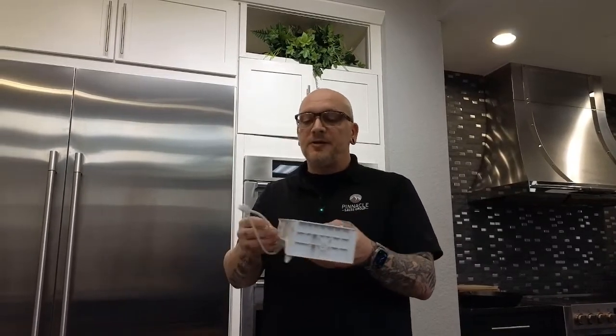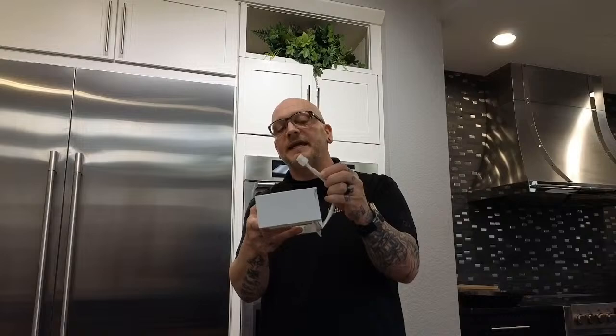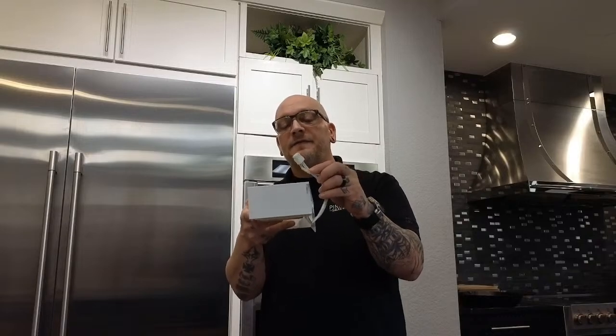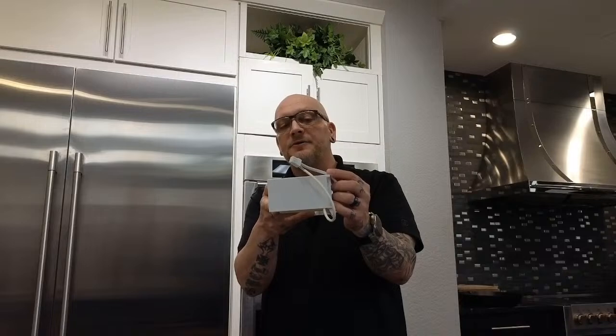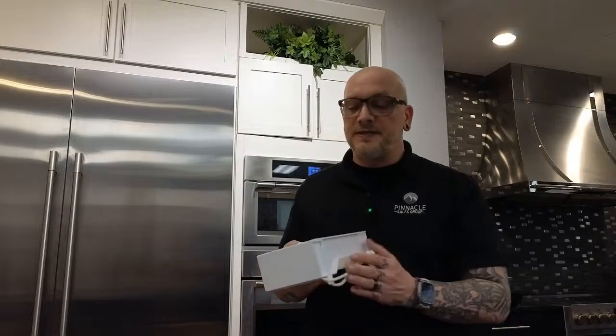But again, going back to the ice maker installation, when you replace these in the combi units, they're in the freezer so you're kind of laying on the floor, and this is located in the upper left-hand corner of the freezer. So that bracket mounted on the side here gets screwed into the ceiling and to the sidewall. Where these wires plug in on that sidewall, there's a good chance that you might have some harnesses hanging out over top of that metal bracket. If that's the case, put your hand up there and push them out of the way, so that you have ceiling and ice maker and you're not pinching the wires between that metal bracket and your ceiling. It has happened. I've been on the phone with technicians before, so just be a little careful, push your wiring out of the way, and then zip your ice maker and mount it. It's one of the easiest ways I found to do it.